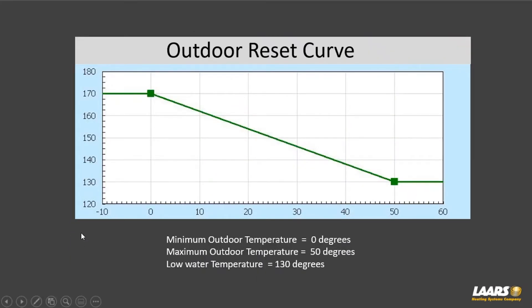I'll talk about an outdoor reset curve and how it works. On the left-hand column is your supply temperature to the system; on the bottom is outdoor air temperature. We provide an outdoor sensor that you install outside and use to set up your curve. For example, on a zero-degree day you might deliver 170 degrees — that's your CH set point. So if you had a CH set point of 180 and a minimum outdoor temperature of zero, at zero degrees you'd deliver 180.